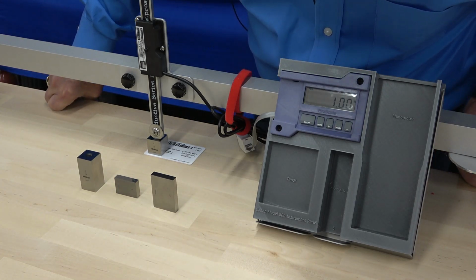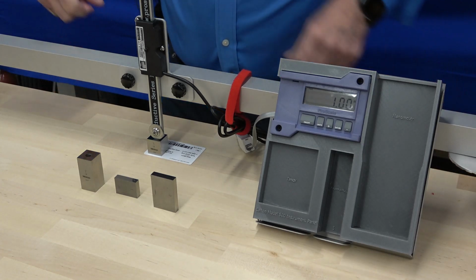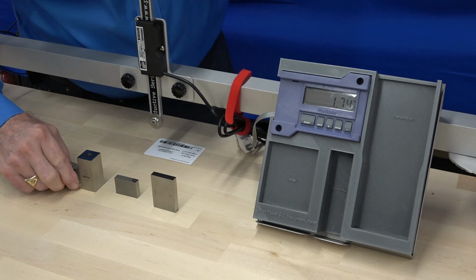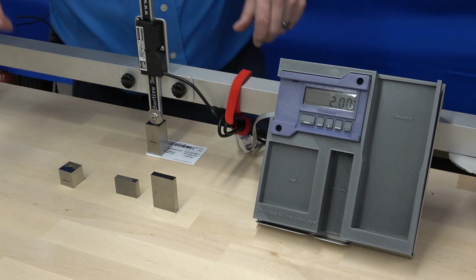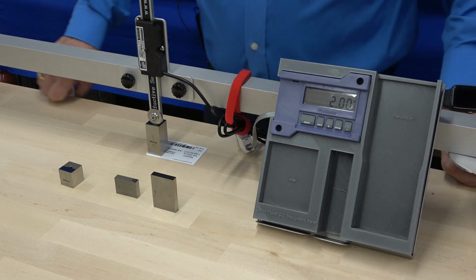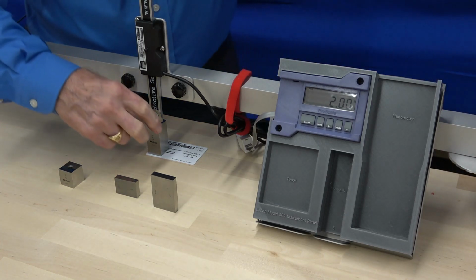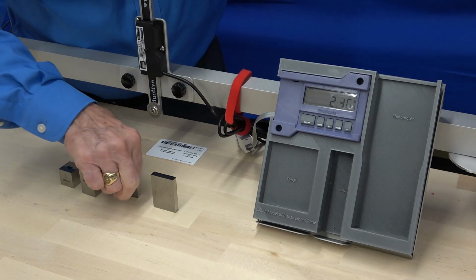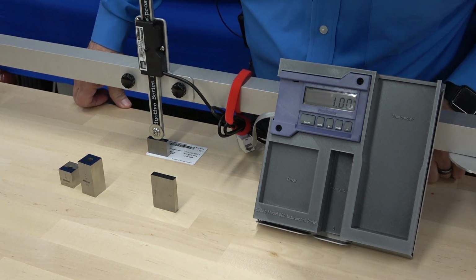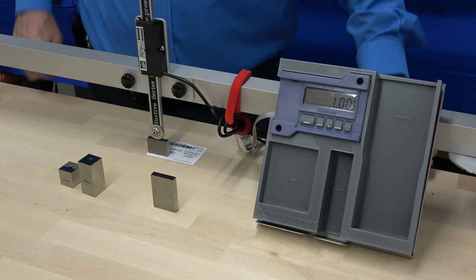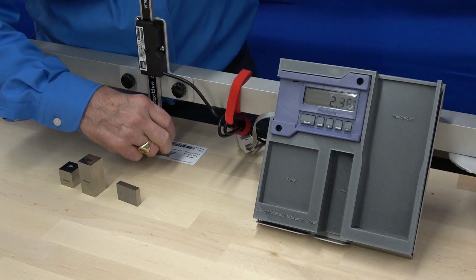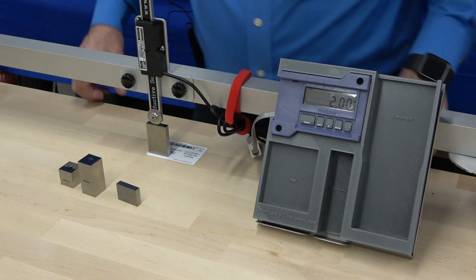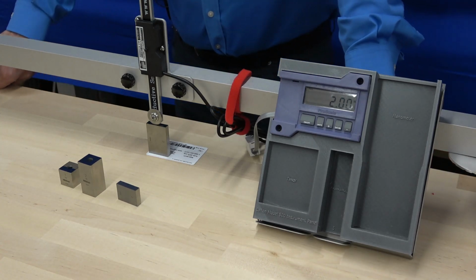Now I'm going to take the 1 inch calibration block, place it underneath the foot of the sensor, and the readout is 1.00 inches. I'm going to replace that now with the 2 inch block and do the same thing, making sure that I don't hit that hole. And now I'm reading 2.00 inches. As I said, you only need one set of blocks, but here I'm using a second set of blocks, and I drop the sensor down and I get 1.00 inches. I replace it with a 2 inch block, and I get 2.00 inches.